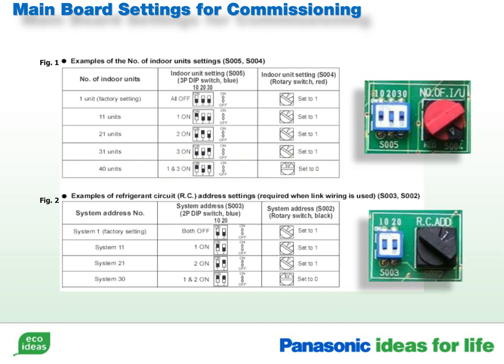Figure 2 shows some examples of the refrigerant circuit address settings. Once again the factory default is both switches in the off position. This would allow you to select a refrigerant circuit address of 1 through 9. If you needed to set the refrigerant circuit to 21, you would set dip switch 2 to the on position, and the rotary dial would be set to 1. These details can be found in the installation manual.